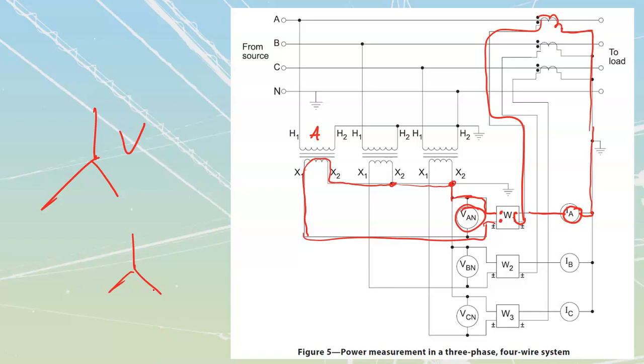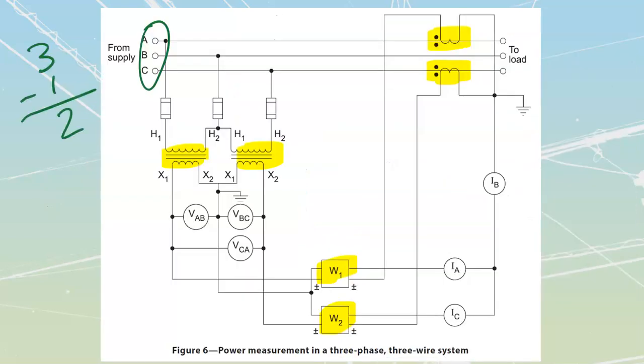It's just a ratio of this PT ratio multiplied by our CT ratio, and that's going to give me what my watt meter multiplier is. Then I just take those watts that I read off the watt meter and multiply them by that multiplier to get the actual true watts on the system.